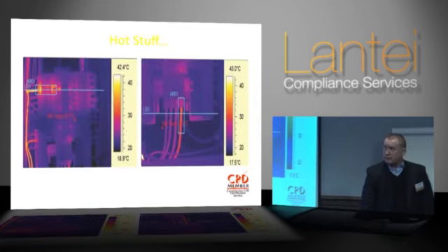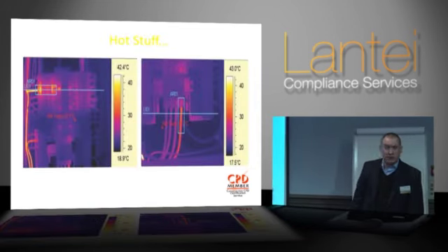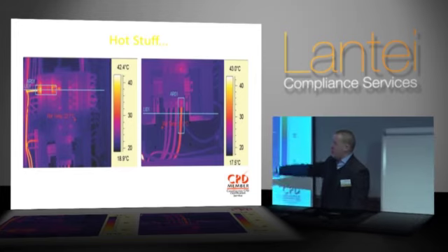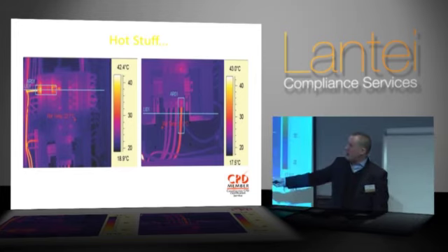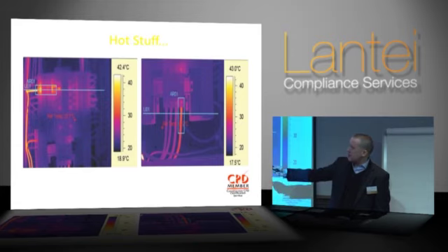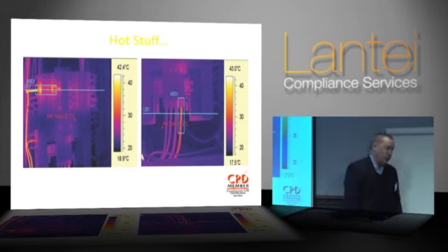And when we look at, I don't know if you can all see them, are they pretty clear for everybody? When we look at the two thermal images on the screen, the one on the left-hand side here is a distribution board. There are your busbars running through the middle. All these are our circuit breakers running down either side of the board. As you can see, one of the circuit breakers is getting very warm. Both the terminals on the busbar, the terminal where the cable is, and the cable itself. We've also got a cable there running very warm. Clearly that's still on, it's still active. But it doesn't take a genius to work out it's not going to be staying live for much longer. That device is going to activate sooner or later. Prime example of what thermal imaging is there to do.